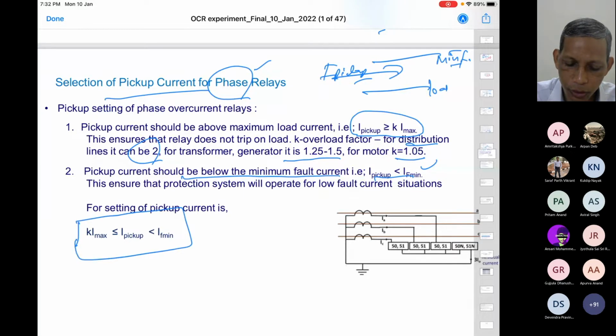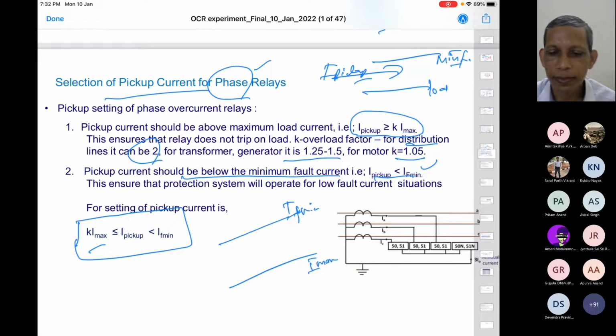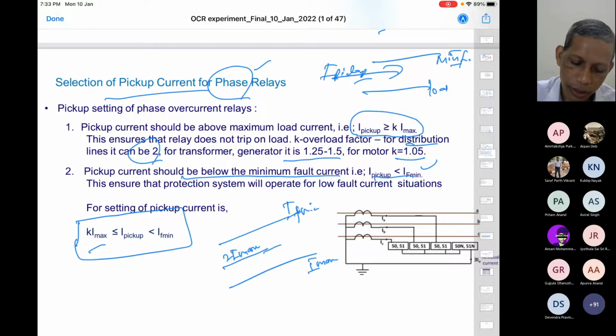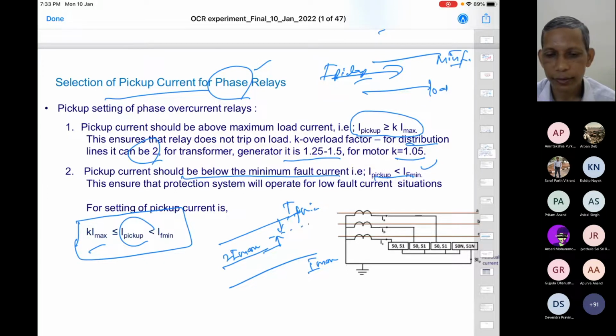So how will we select the pickup current? Pickup current should be greater than K Imax. For a distribution line, it should be twice Imax, and it should be less than I fault minimum. So that's my point now. Let us say this is I fault minimum, and let us say this is the Imax level, and this is twice Imax. So what is the I pickup setting? This guideline says that it should be greater than this and less than this. So I can select I pickup here.